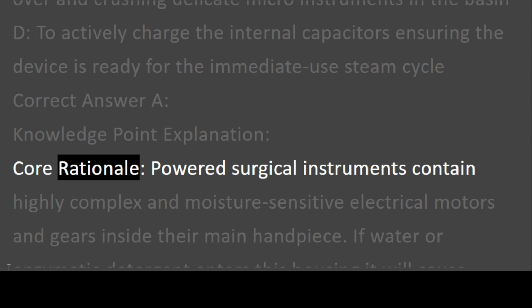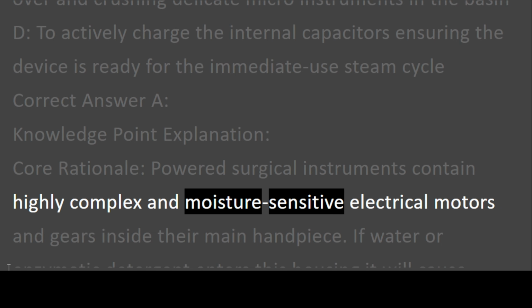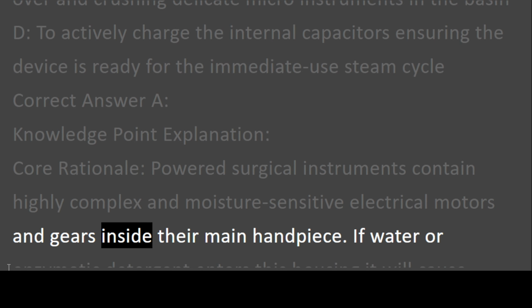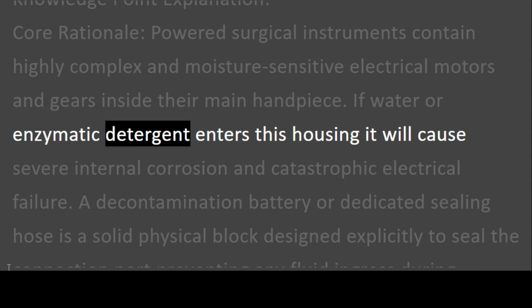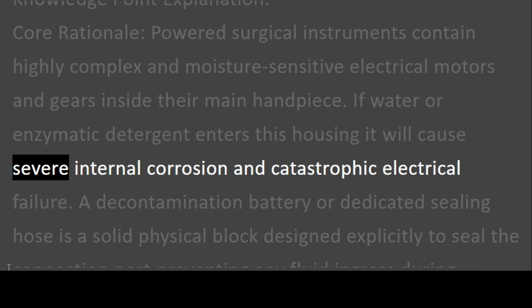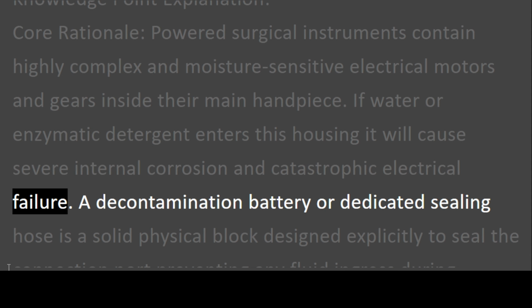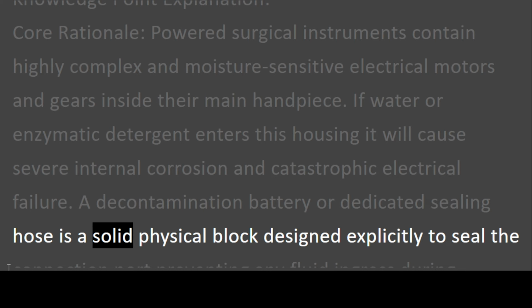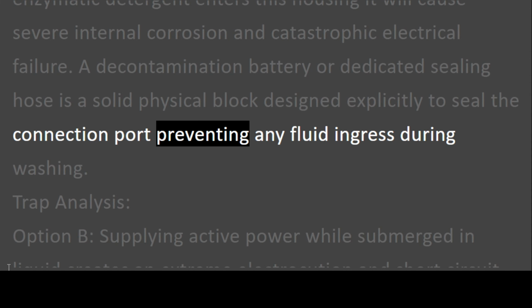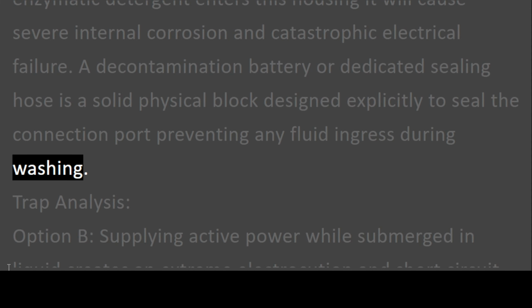Core rationale. Powered surgical instruments contain highly complex and moisture-sensitive electrical motors and gears inside their main handpiece. If water or enzymatic detergent enters this housing, it will cause severe internal corrosion and catastrophic electrical failure. A decontamination battery or dedicated sealing hose is a solid physical block designed explicitly to seal the connection port, preventing any fluid ingress during washing.